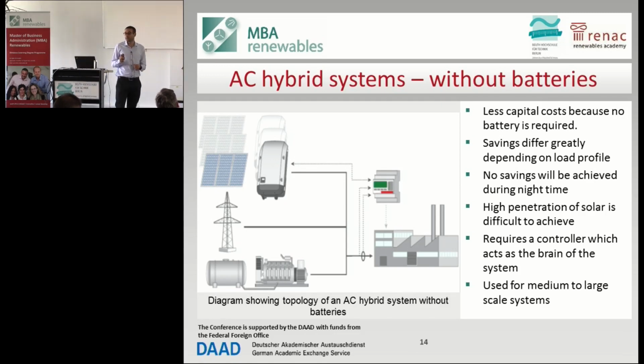It's sometimes called on-grid PV diesel. Here you will have a load, and you will have a diesel generator or the grid. One of them is the grid former. You always need an element which makes the grid. And then you plug in an on-grid PV inverter. I like to think of on-grid PV inverters as slaves. They cannot be a master in a circuit. Wherever they get the grid, they just synchronize with it and produce electricity. So it will never work alone. You always need one of these two, and that's what Lars also mentioned yesterday. This system is very straightforward. You just install it in mines, in schools, in factories, in all these places.